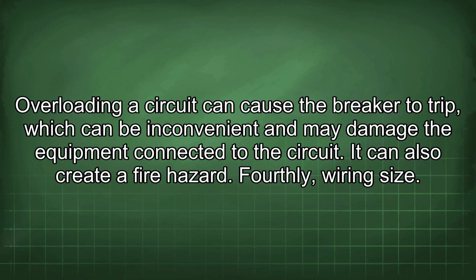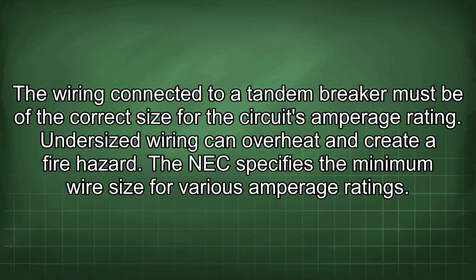Fourthly, wiring size. The wiring connected to a tandem breaker must be of the correct size for the circuit's amperage rating. Undersized wiring can overheat and create a fire hazard. The NEC specifies the minimum wire size for various amperage ratings.